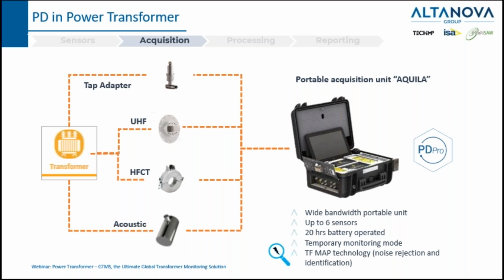Regarding the acquisition, you can see here an example, a schematization of the transformer with several sensors, the tap adapter, the UHF, the HFCT, and also the acoustic, connected to an acquisition unit. In this case, you can see on the right our portable Altanova Aquila PD acquisition unit. This is a wide bandwidth portable unit where we can connect up to 6 sensors to have the best coverage of partial discharge detection and identification in the whole transformer.